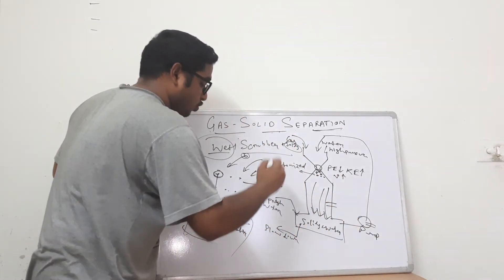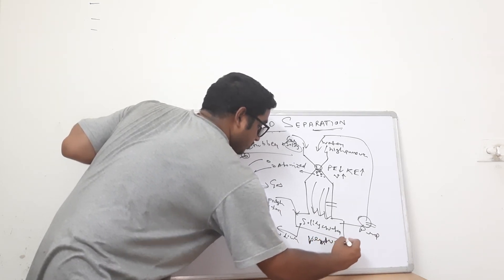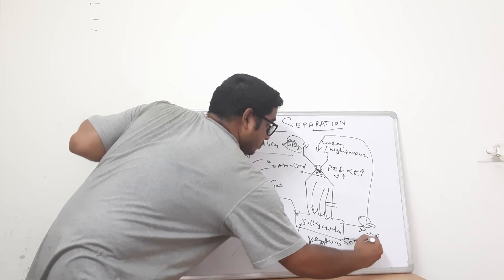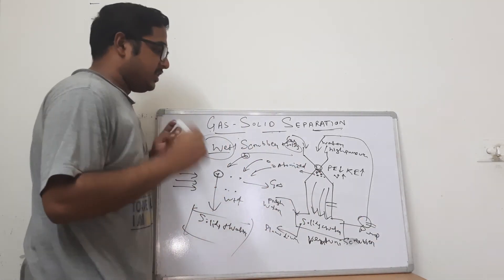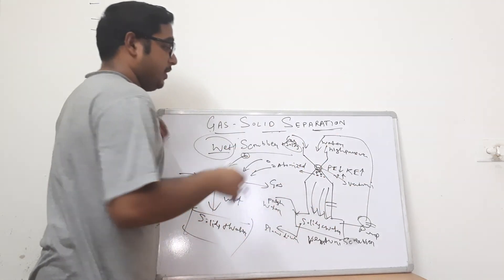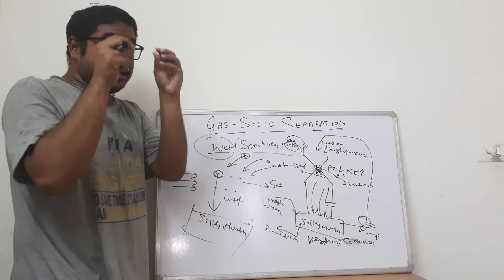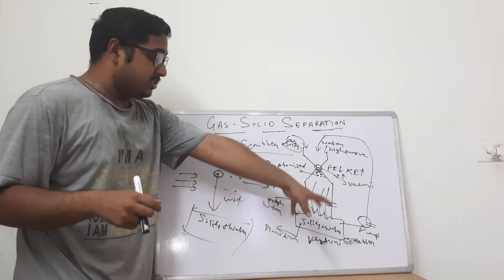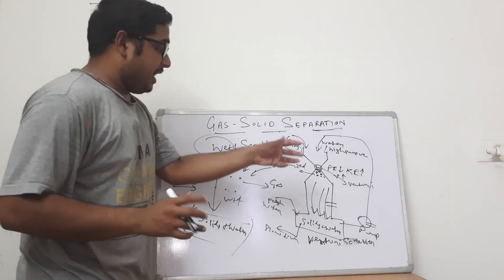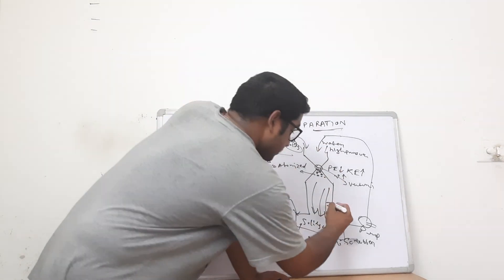This is the venturi scrubber — a very popular practice in the industry. At the venturi constriction, the potential energy converts into kinetic energy, atomization of water droplets takes place, the droplets take off the solids with them and deposit at the bottom in the reservoir, and are recirculated in the system. Continuous purging and fresh water inlet are maintained such that the atomization energy drives out the solids from the system and the fresh gas exits.